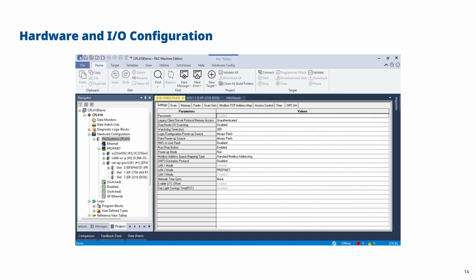Under the memory tab, you can select the memory sizes. A lot of the memory sizes are fixed, but for some of them, like registers, you can increase the default size, and it uses more memory from your 64 megabytes in the case of a CPL410, but it allows you to have more storage for data. You can also configure things like %W. You can configure a particular set of memory that's used for fault checking, for fault bits. They're called fault locating references. And you can also configure the amount of memory that's reserved for symbolic variables.